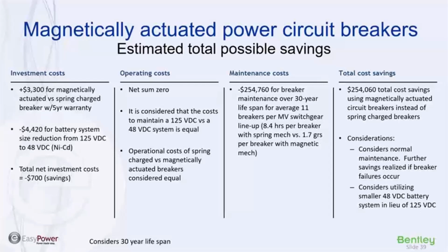So what we see is that if you use this technology, you would have a little bit of an increased upfront investment cost. One of the interesting side effects is when you look at the control power that is needed to supply for the operation of the breaker and to maintain the breaker state, a magnetic breaker actually requires less in terms of power consumption, so you can actually save on a battery system. So you would have some difference in the investment cost. From an operating cost, right? It's more or less the same as a spring breaker, but the maintenance cost would be significantly less over the lifetime. Okay.